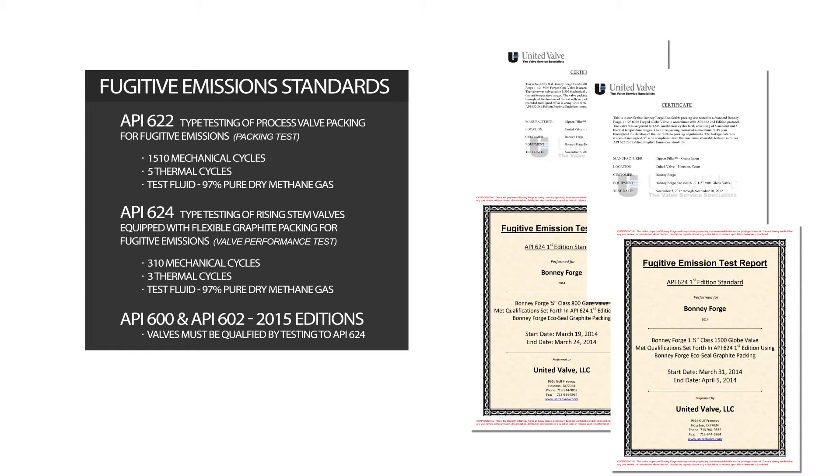Next came API 624, which is a type test for valve performance with packing that was tested to API 622. The test requires 310 mechanical cycles, 3 thermal cycles, and no packing retorque. Test fluid is 97% pure methane gas. API 600 and API 602, new editions in 2015, require valves to be tested per API 624.